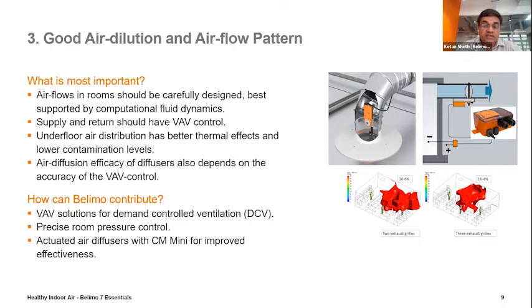Whereas you can see on the right hand side, the first picture, we have got a 1 Newton meter actuator which can have a much better control for a diffuser in terms of controlling a good amount of CFM in that area, which also helps in a better way of demand control ventilation for the VAV, and which results in a much better, or maybe a precise, room pressure control.